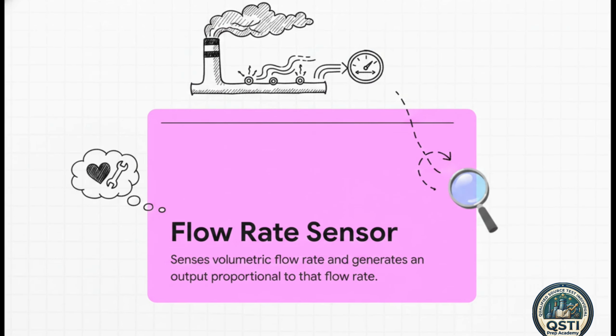Now, inside that entire CERMS setup, you've got some specific, vital organs. The most critical one, highlighted in PS-6, is the flow rate sensor. This little guy senses the volumetric flow rate, basically the speed and volume of the gas moving through the stack, and generates an output proportional to that flow. But here's the kicker. It absolutely must have provisions to check its calibration drift individually for each parameter it measures, like velocity or pressure. It needs its own targeted health check.